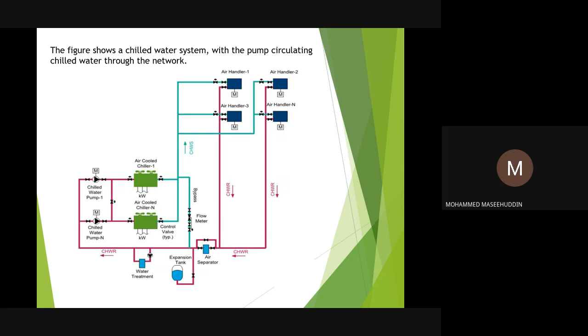This expansion tank provides both pressure and water, which is lost either due to evaporation or leakages within the piping system of the chill water. And this water is treated, because since it's a closed loop and a closed circuit, the water gets contaminated within the pipes and within the system. So it is treated by an automatic dosing unit, which has chemicals inside and a sensor which senses the conductivity of the water. We preset a certain conductivity, which is specified by DEWA. A certain number of microsiemens per centimeter of conductivity is needed for the water to be within the loop.